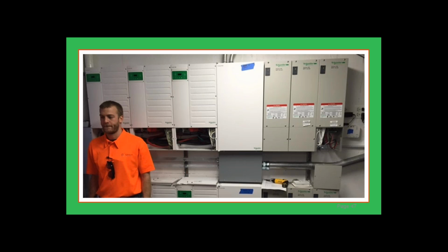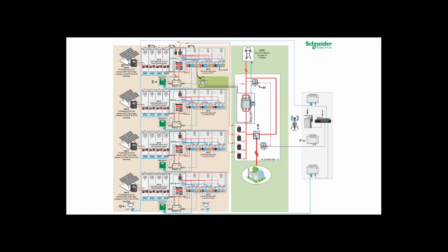These photos were taken last year when the system was commissioned. You can see the charge controllers on the right, inverters on the left. So this shows a screenshot here of what we call a multi-cluster. This is an example of multi-unit XW system where you could have up to 12 XWs and up to 16 MPPT-80 charge controllers. So if you follow the blue line, you can see that the inverters are in the network daisy chained with the battery monitors, and those are all dedicated to one ComBox. And then all of the solar charge controllers are dedicated to a second slave ComBox, and then a master ComBox is used to aggregate the data from both slave ComBoxes onto a single web page.